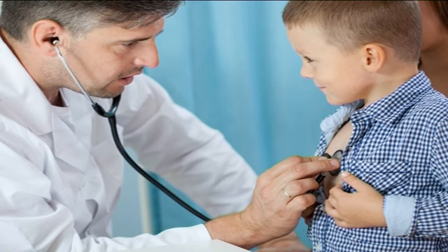Place the earpieces of the stethoscope in your ears. Place the diaphragm of the stethoscope over the brachial pulse. Close the valve on the air pump. Turn the knob to the right to close. Pump air to inflate the cuff until the dial points to 170. Deflate the cuff slowly and at a constant rate by turning the knob to the left slowly.